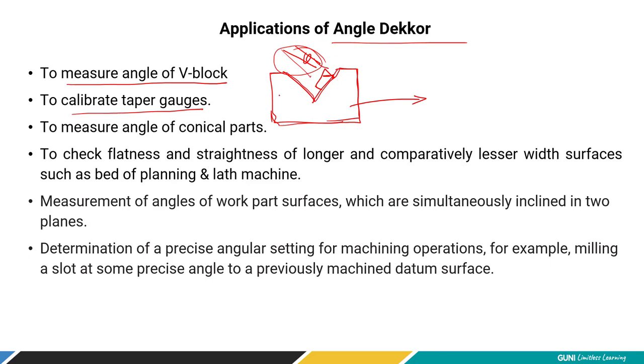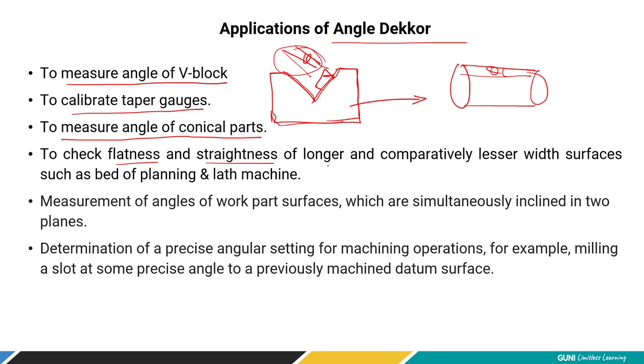The Angle Dekkor is used to measure the angle of conical surfaces — which are cylindrical in cross-section but have some taper. It is also used to check the flatness and straightness of longer surfaces with comparatively lesser width.